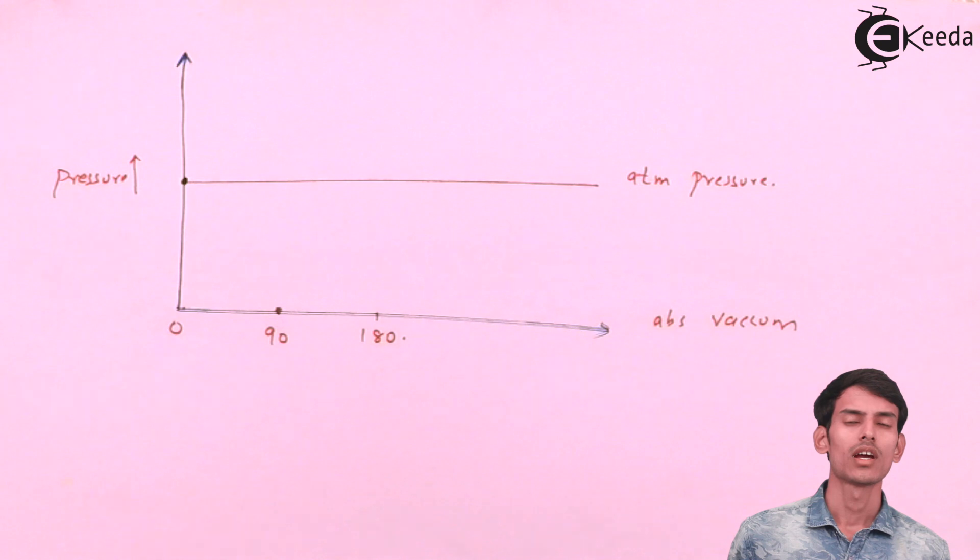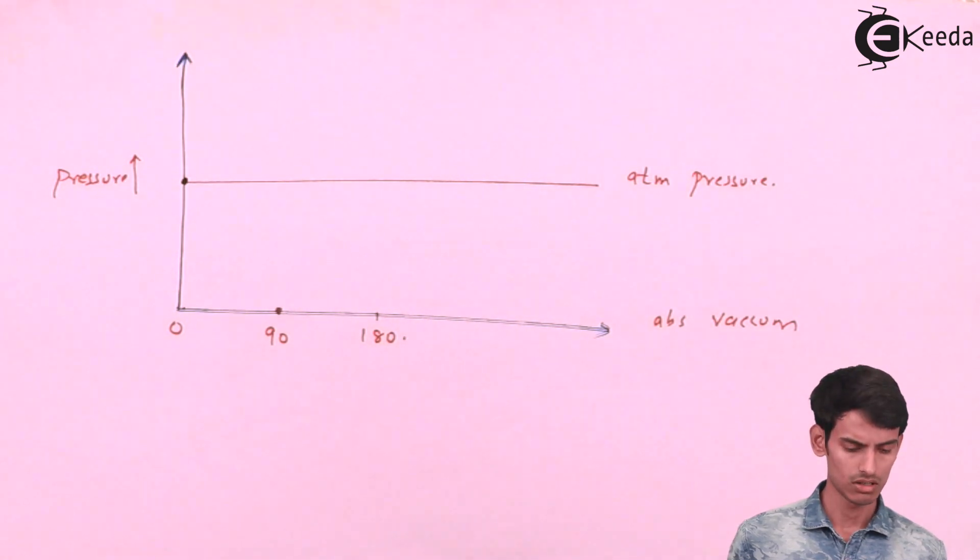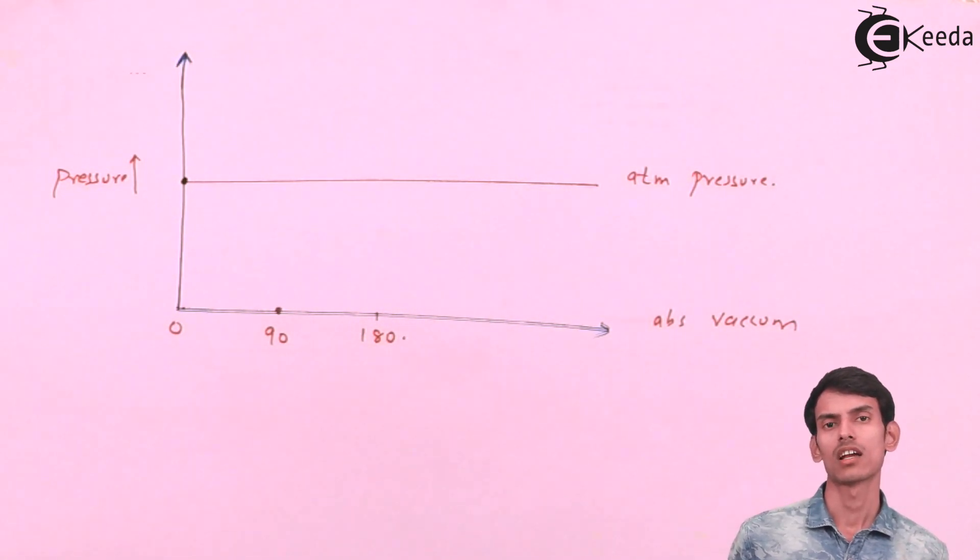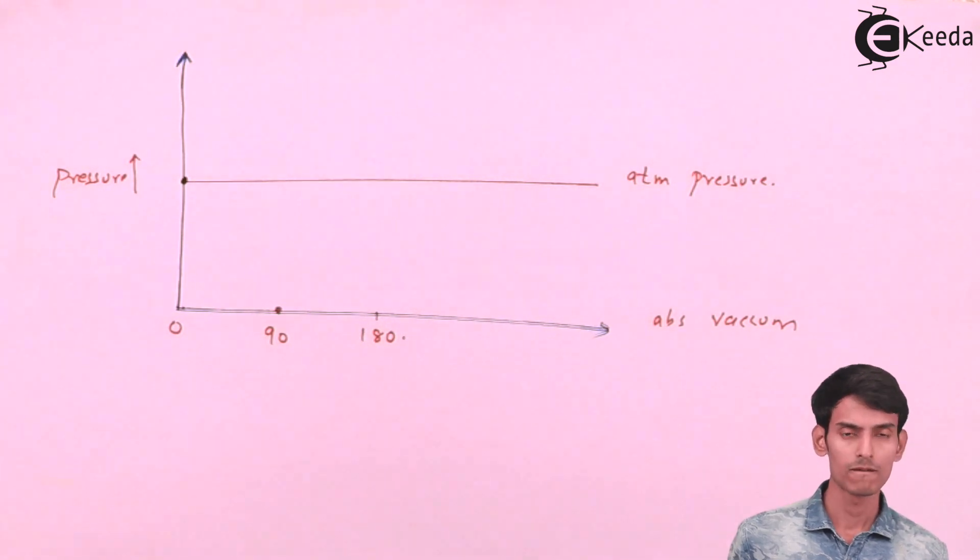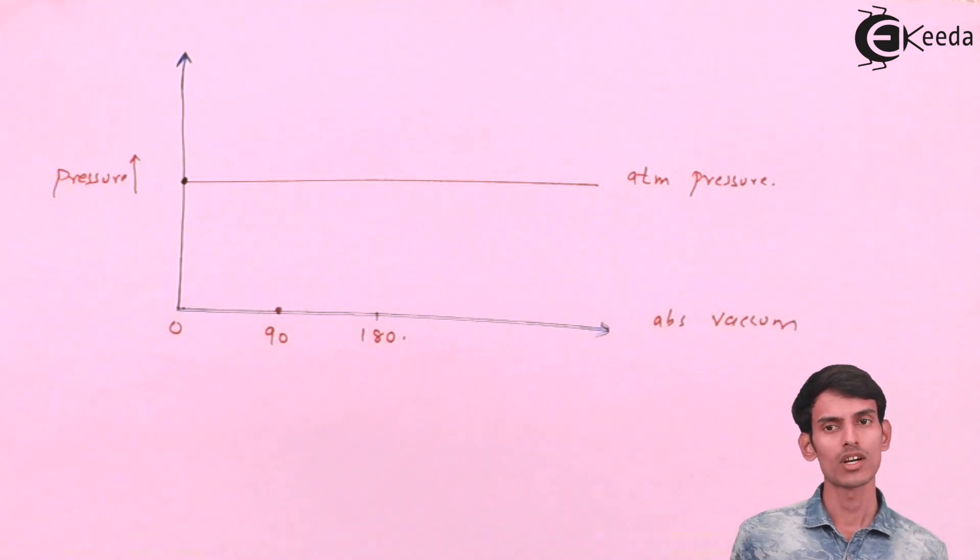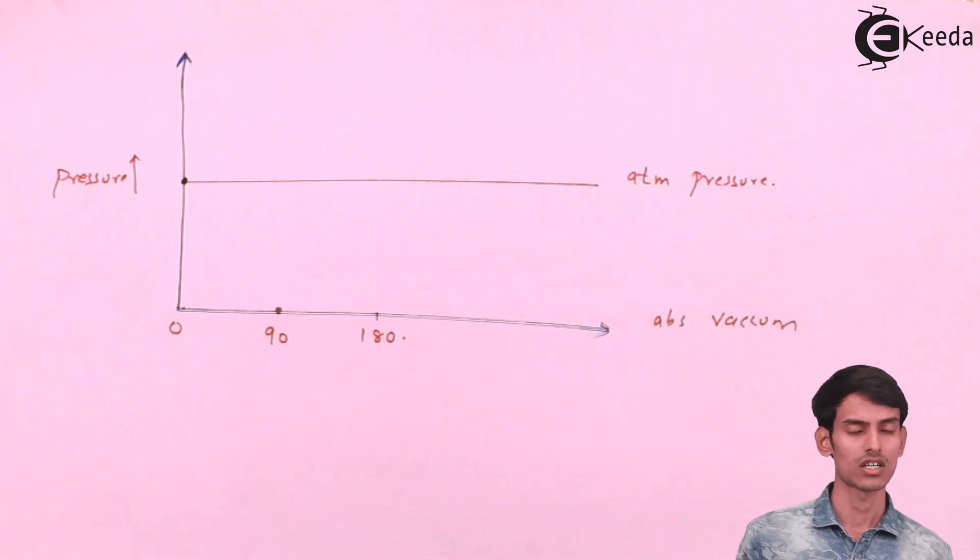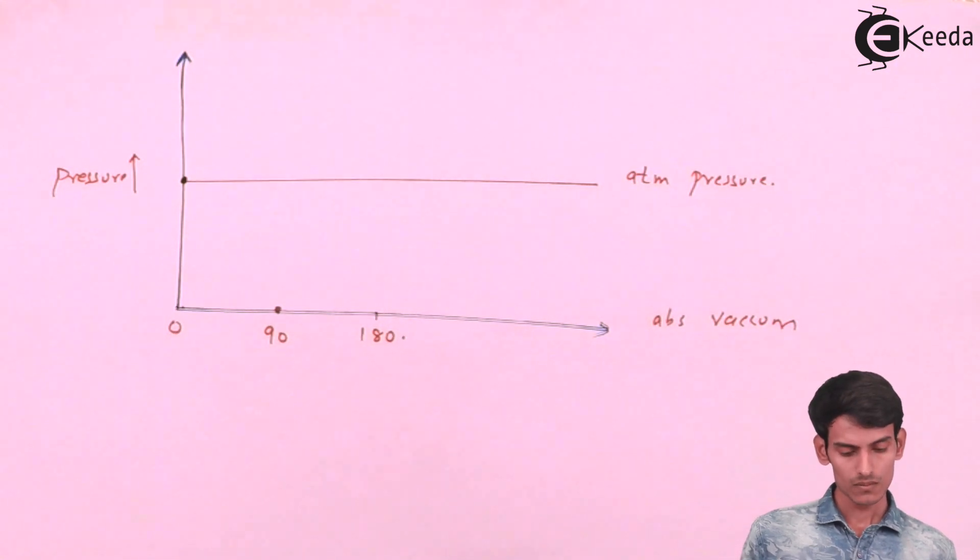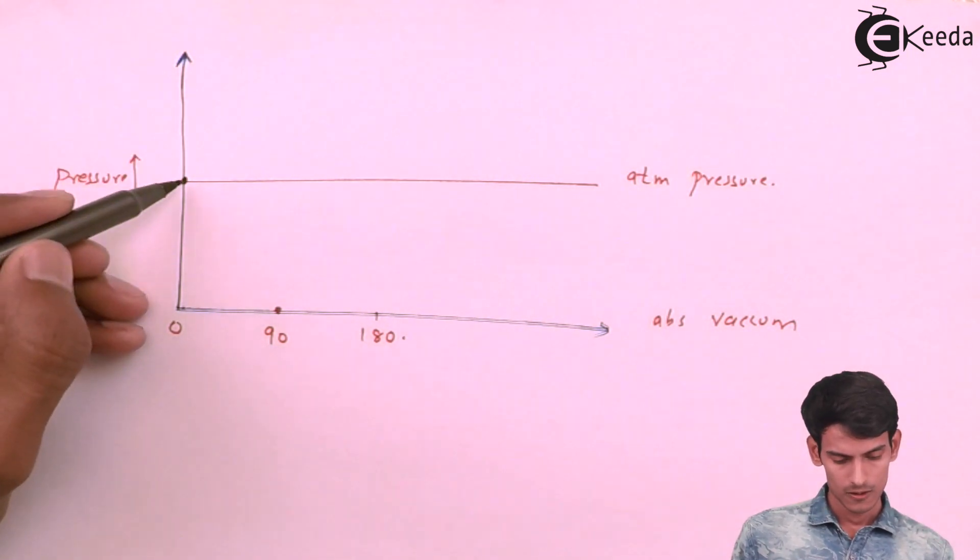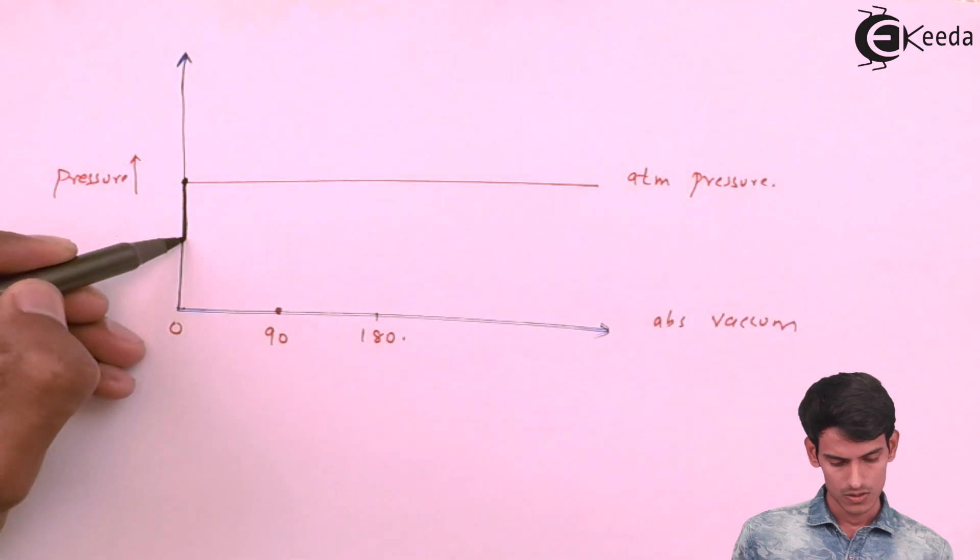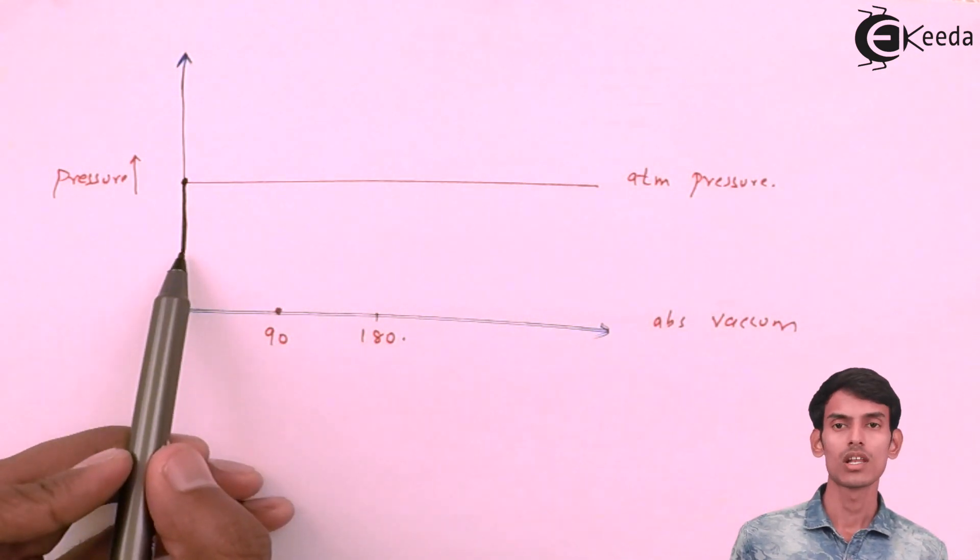Now, when we drew the indicator diagram earlier, we had like a rectangle kind of thing. Because that time we only had HS and HD. So now, when I am drawing, we have already seen the effect of acceleration now. So there is one more head that comes in that is HAS, the effect of acceleration at the suction side. So when the pump is creating vacuum, it has to create vacuum that is equal to HS plus HAS.